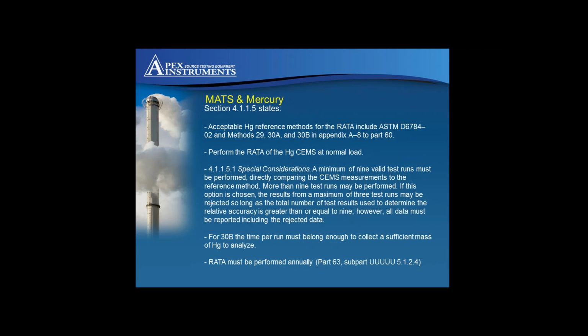Validating mercury measurement systems: the Ontario Hydro method, Method 29, 30A and 30B are all acceptable reference methods. We would suggest, though, that 30B is the simplest method, and taking into account that PS12B is based upon Method 30B, it is almost identical to a continuous sorbent trap monitoring system. Other specification details for performing a RATA are: the RATA must be performed at normal load. A minimum of 9 runs must be performed during the RATA. However, up to 12 runs can be performed to allow you to discard 3 runs. Keep in mind, though, that the 3 rejected runs must still be reported.